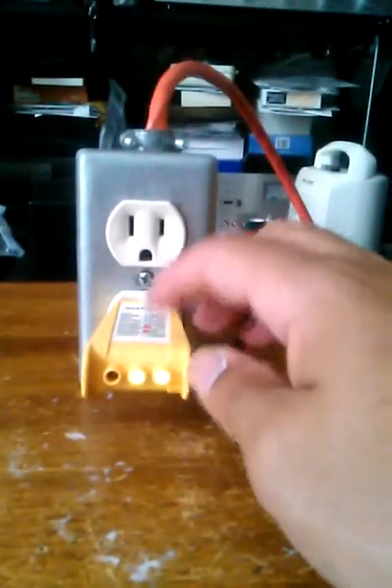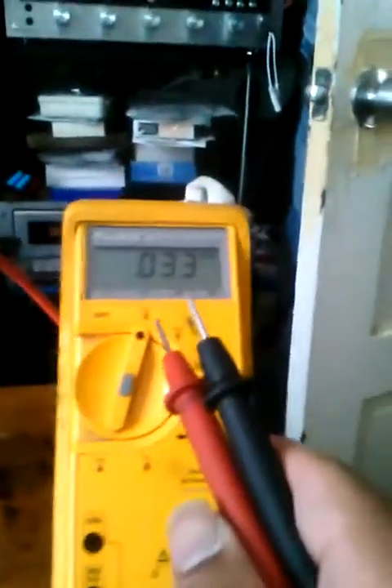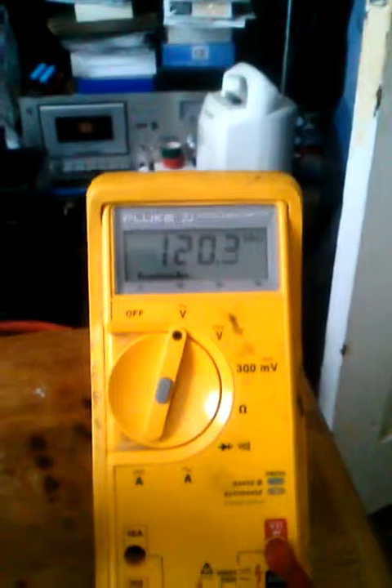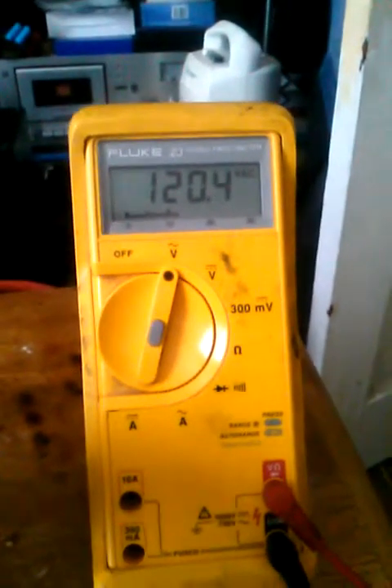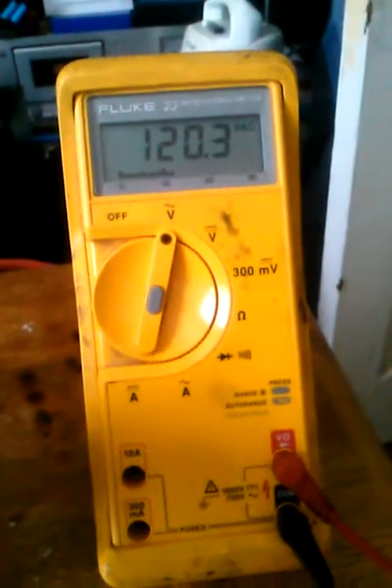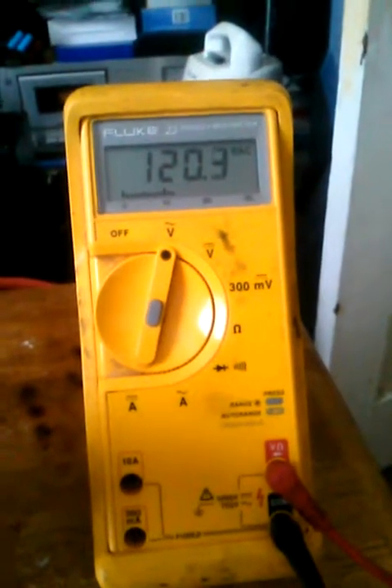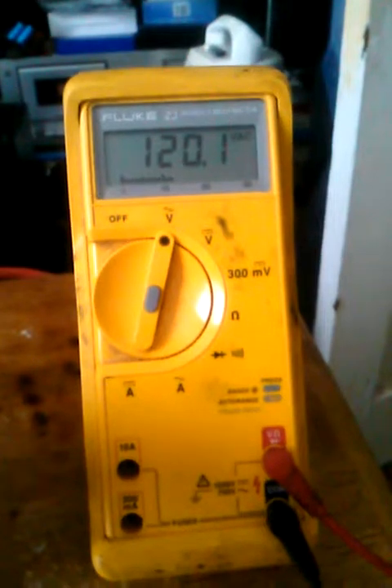Now, to test it, if you don't happen to have this receptacle tester, you can use a multimeter, which I've shown in previous videos. This is a Fluke 23 Series 2 multimeter, and if you wanted to test for proper polarity and grounding, you would simply do this. You take your two prongs here, and it doesn't matter which prong you use. So this side is your hot, so you stick your prong inside the hot side and just touch the screw, and it should read 120 volts, or 110 volts, or 115 volts, depending on how many circuits you have on the line, if you have a branch circuit. Which tells me, one, this outlet is properly grounded and is in the proper polarity setup.